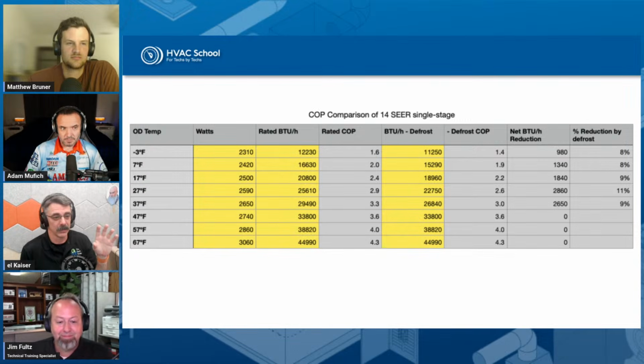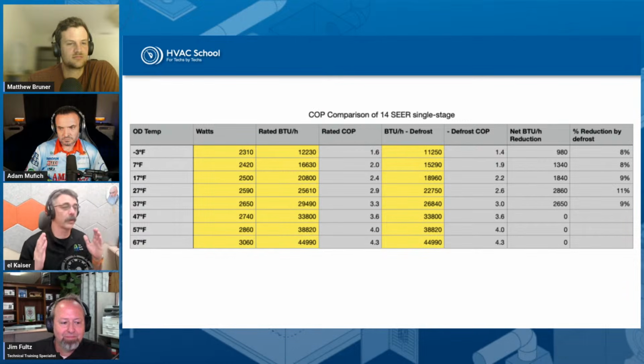Right. This is not your Mitsubishi Hyperheat. This is not the Carrier Greenspeed. This is a single stage 14 SEER bare bones builder grade heat pump. And with the defrost cycles factored in, we're still seeing a COP of 1.4 at -3 Fahrenheit. So to me, that negates the entire argument.